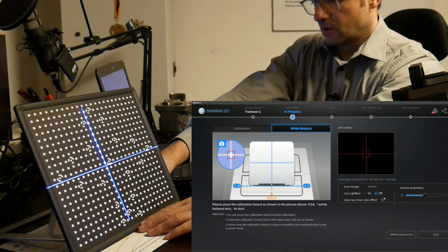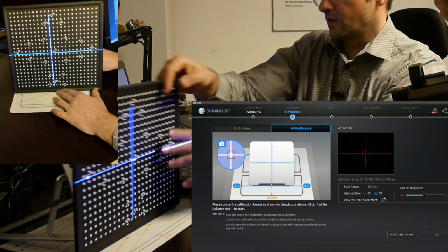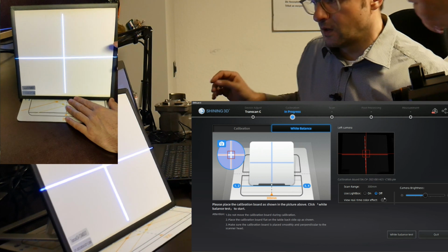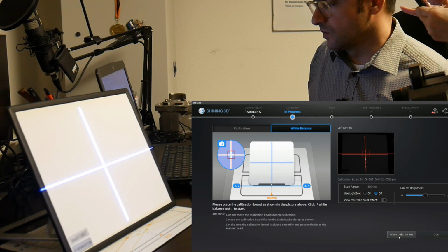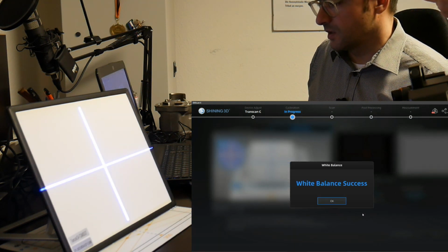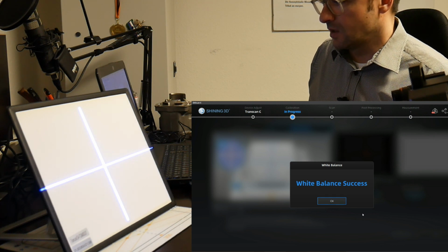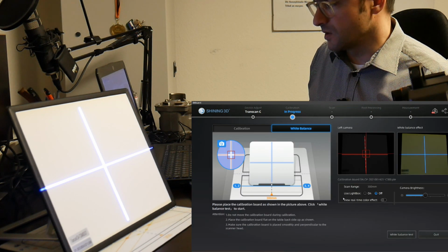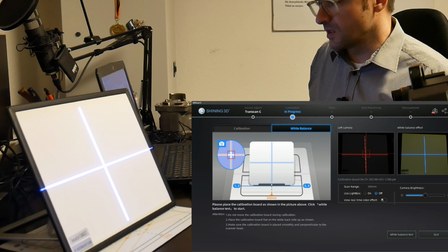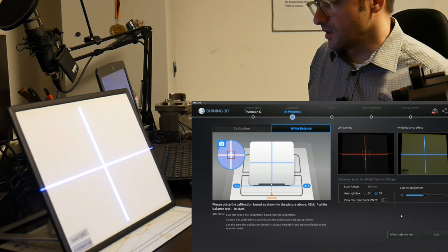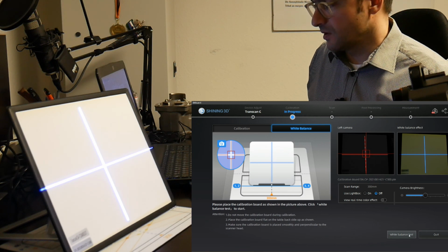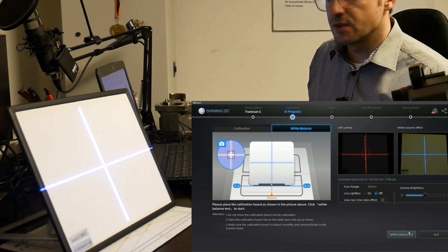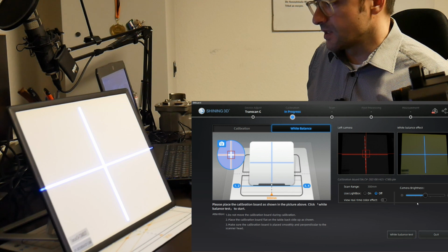Therefore, don't forget to go back into your initial position for the calibration board and then turn it around as it's shown on your screen, in the example to the right side of the calibration board, and you do white balance tests. That is a one-point calibration for the RGB colors. Everybody who has had design topics knows what it means: all your RGB channels over the white light are balanced to one point where it's right. That's not the perfect condition to scan real-life colors, but it's a very important one, and something that should be done in all professional scanners.